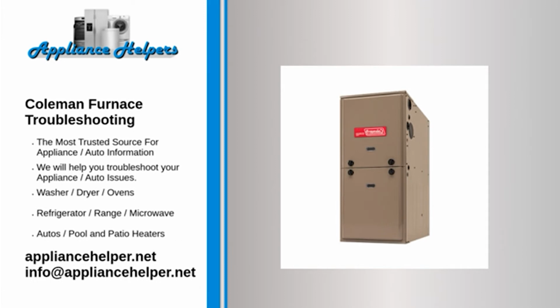Blowing too much air. The control board is experiencing difficulty. The board's relay that regulates how much voltage is sent to the blower motor is defective. You will have to replace the control board.